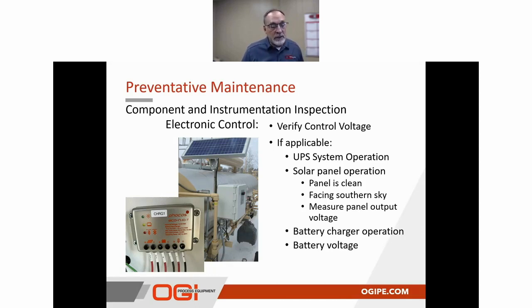Finally, we have the battery itself. Depending on what its output is doing or what its purpose is, most of the time we're looking at a 12-volt battery that's going to have a range of about 11.5 to 13.5 volts DC. One of the things that's critically important is that the battery be tested annually under a load, performing a load test on the battery to ensure that it has the integrity to support your operation throughout the year. The hard thing about that is that batteries you would use for this system do have a shelf life.